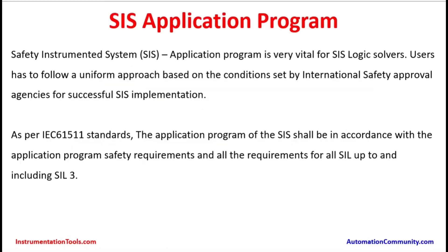The SIS Application Program is vital for SIS Logic Solvers. Users have to follow a uniform approach based on the conditions set by International Safety Approval Agencies for successful Safety Instrumented System implementation. As per IEC 61511 standards, the application program of the SIS shall be in accordance with the application program safety requirements for all SIL up to and including SIL level 3. This means programs by different manufacturers on different applications should follow a uniform standard.